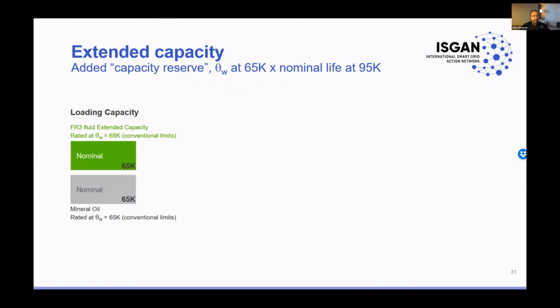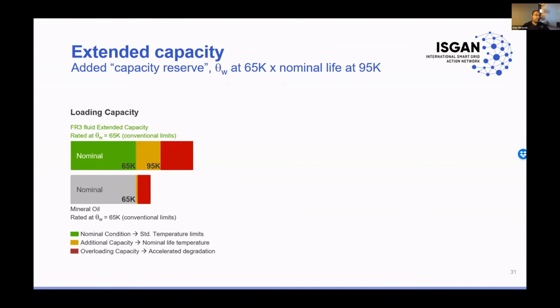When you bring this to the transformer perspective, you have the transformer designed to the same 65 Kelvin average winding rise, traditional, in all standards, and this is the brownfield solution that Angelo was presenting. But if you have a transformer with mineral oil designed to 65, nominal life happens at the same point of 65. When you have the transformer designed to 65 and you are using a natural ester, the nominal life will only happen at 95, 30 degrees more.